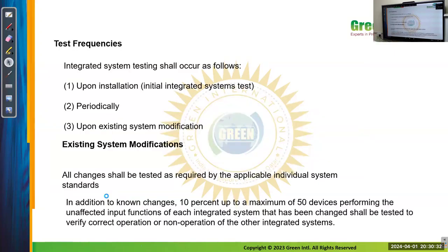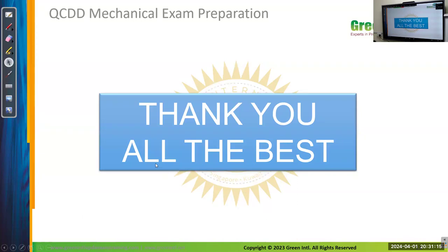So this last one means 50 devices? Yes, up to a maximum of 50 devices. 10% up to a maximum of 50 devices. Is it 10% or 50 devices? Yes, 50 devices, not 50%. No, 10% of the system or 50 devices. 50 devices of the system. For example, if I change 50 devices, you have to perform the integrated test. Okay, so this is a small topic. You can expect a maximum of one question from this.